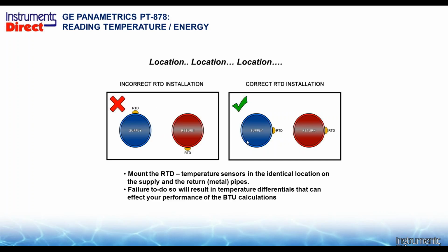Strapping on temperature on the outside of the pipe is an important point that you need to get over. Customers will say, well, it's not wetted, so it's not exactly the same temperature as it is on the inside of the pipe. When calculating BTU, the key point to the equation is temperature differential, not exact temperature. The reason these strap-on RTDs cost so much is they are precision calibrated matched pair RTDs. When you put them on the pipe, it will be better than 1%. So that's the key to the success of any BTU application.